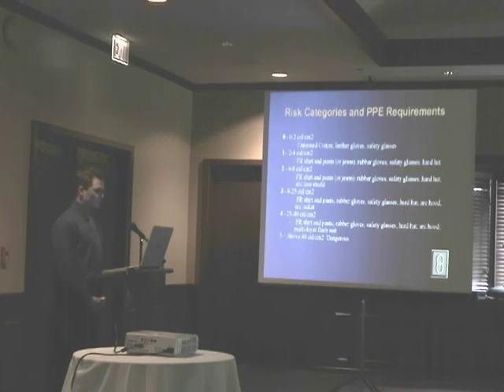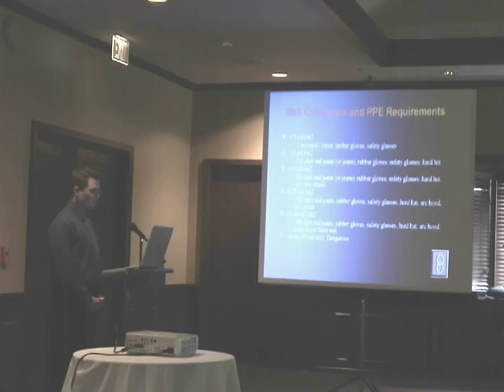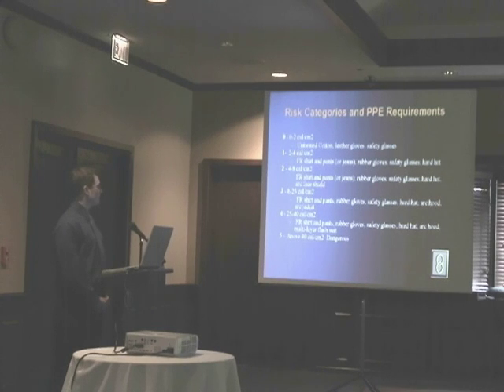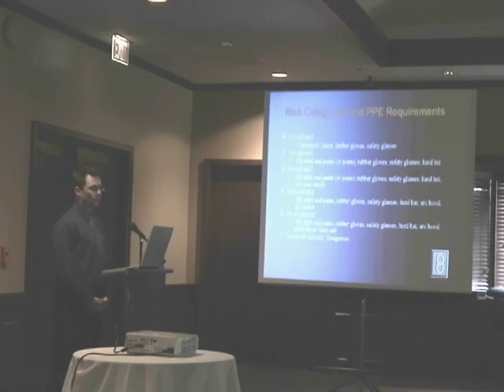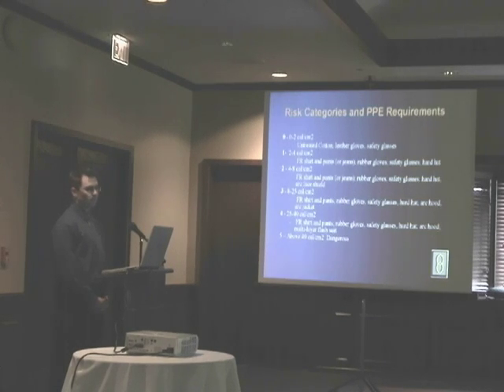Now, your 1, you're getting into 2 to 4 calories per centimeter squared. Not a big jump yet, but you still want to be wearing rubber gloves when you're working on this and a hard hat. Also, you want to make sure that you're wearing a flame-resistant shirt and pants, like I said before, or jeans. When you get to category 2, you got 4 to 8 calories per centimeter squared. This is including all of the previous and adding on an arc face shield, which can be attached to your hard hat and will protect your face from any explosions or flashes.